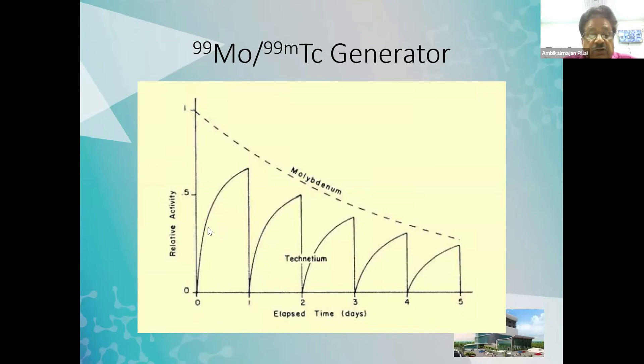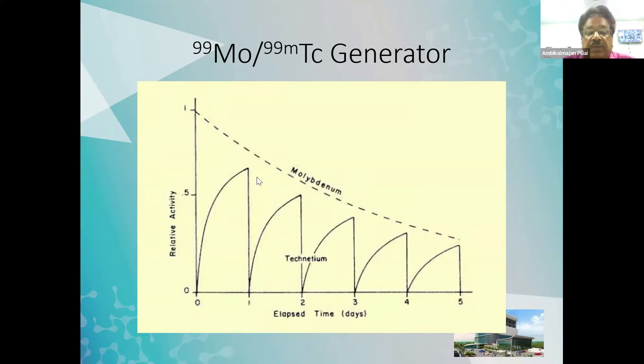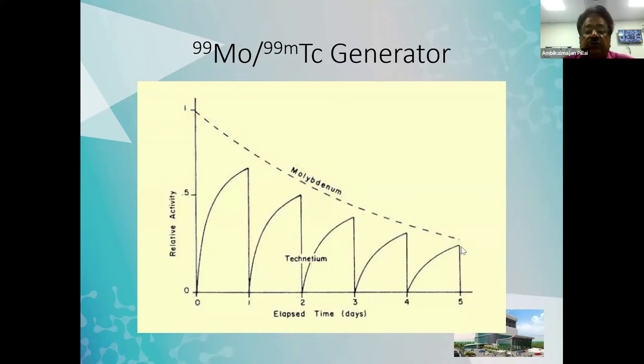Then the activity will start growing and come to about 650 to 700 millicuries on the first day. Then we remove the pertechnetate from it, and it will come back to zero. Again it will grow on the second day, but the overall activity will reduce. Then we do a second elution on the second day, then elute on the third, fourth, and fifth days. If we do not elute, the technetium will also decay in the same manner.